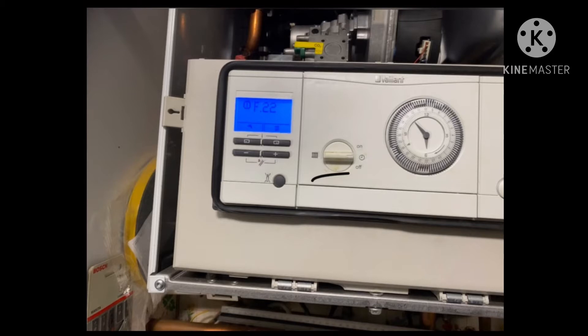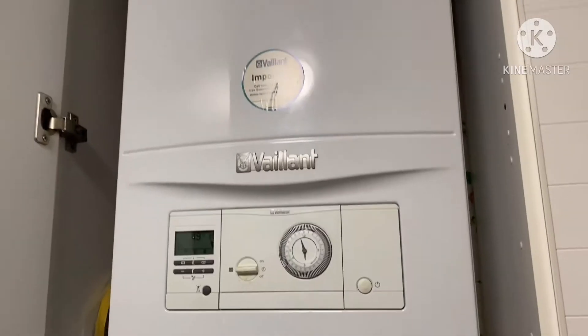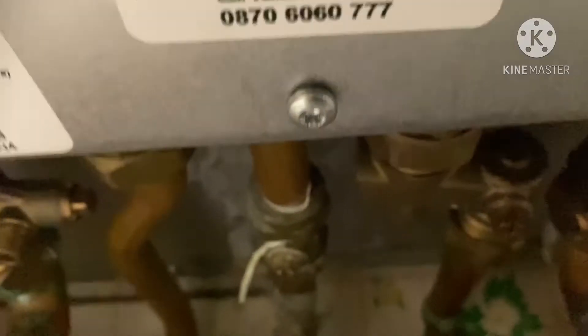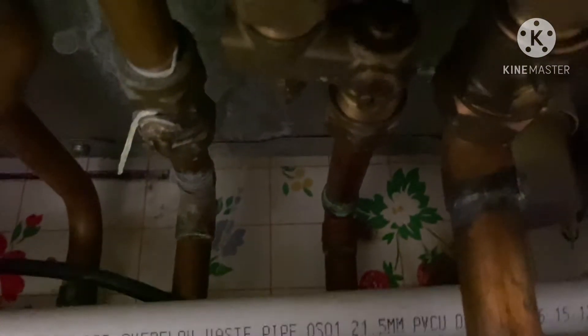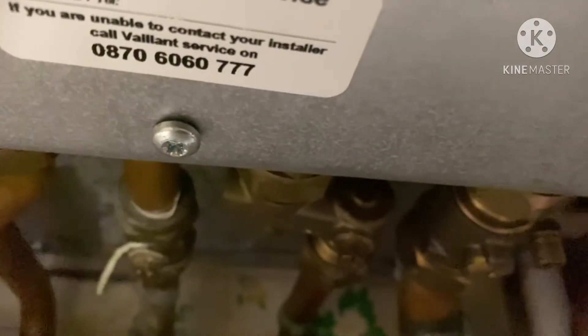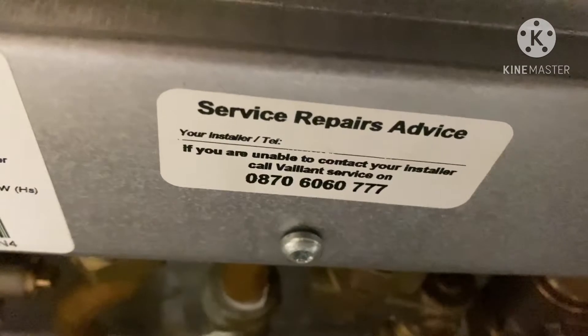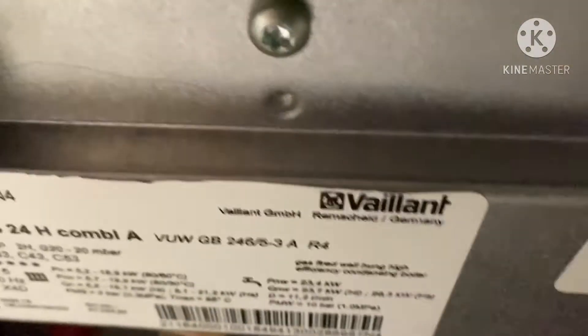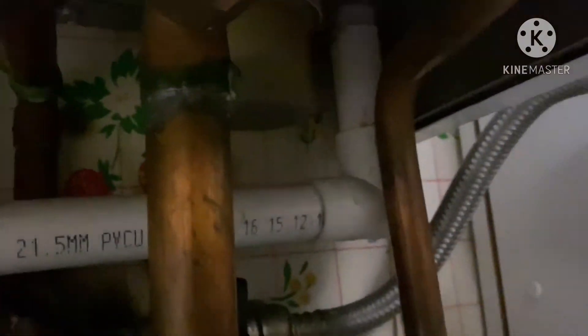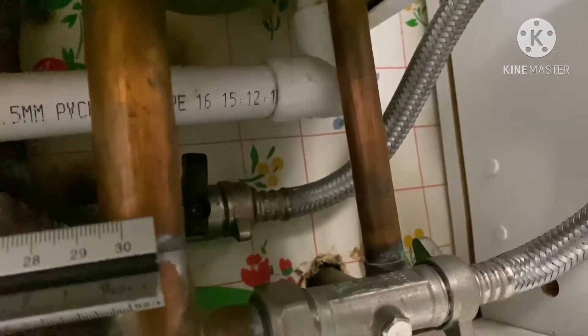Hello guys, today is the Vaillant boiler error code F22. F22 means your pressure is low, you must refill the pressure. On this boiler, where I show the screwdriver, on this side there are two knobs — one here and one gray color — two knobs: ecoTEC Pro and ecoTEC Plus.